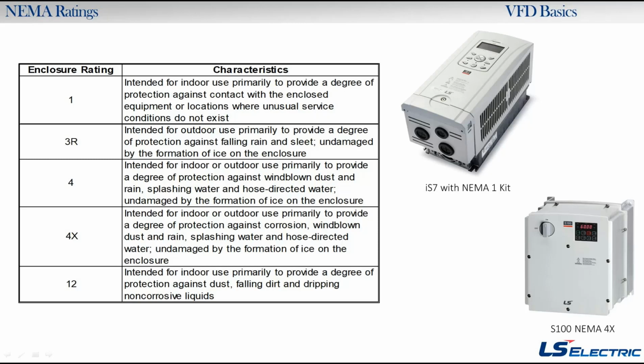And this is what most people are commonly putting on the wall, okay? So you have a drive on a wall, you don't want people to get zapped, you buy a conduit kit or a NEMA 1 kit. Moving on, we have a NEMA 3R, and a NEMA 3R is usually an outdoor rated cabinet. There are not many drives that are just standalone 3R rated, so we do offer enclosed packages that we could quote for NEMA 3R. We could do a bypass or a non-bypass for you. But that's just outdoor rated. Usually it's painted white, good for rain, sleet, snow, and any kind of ice forming on there, as we list here.